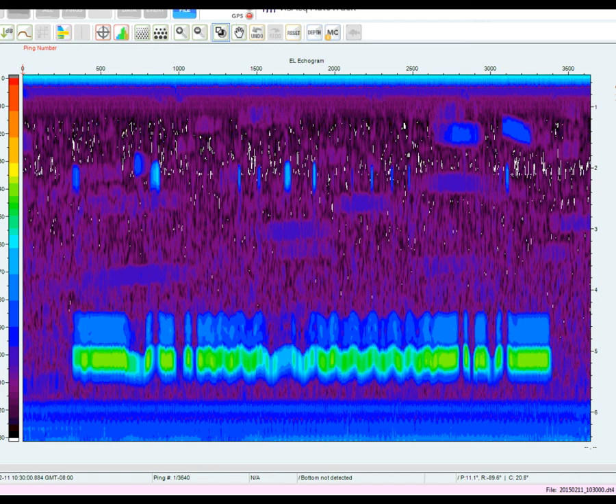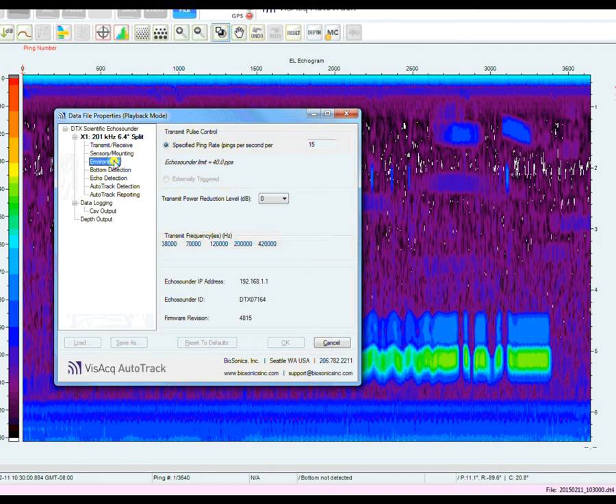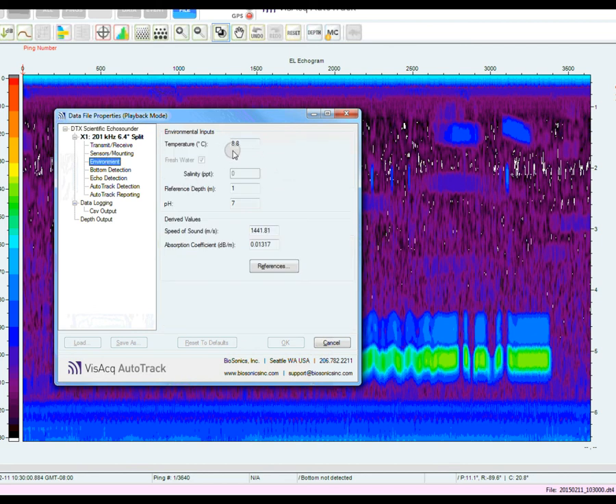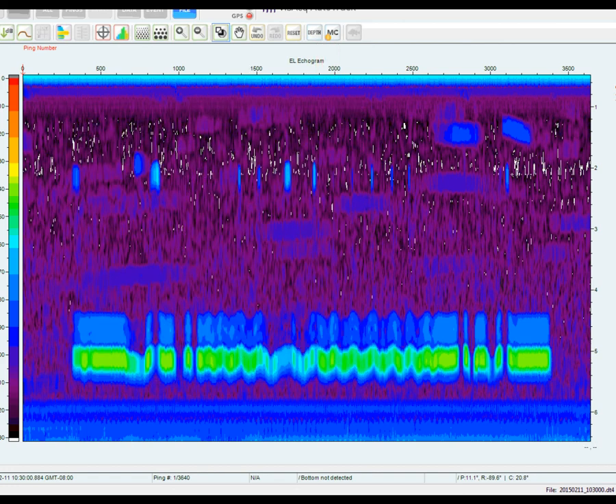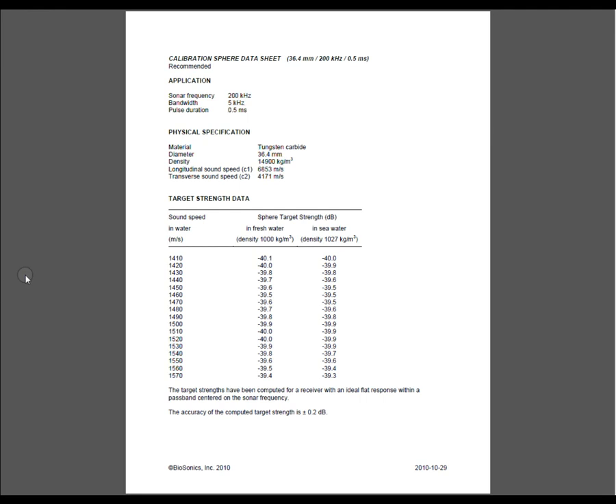VisAcq, we'll go to Playback, View File Collection Settings, and then down in the Environment tab. So you can see we entered a temperature of 8.8 degrees Celsius. We are in fresh water, and if we look, our calculated speed of sound is 1441 meters per second. Okay, so now we'll go back to our sheet, and 1440, that's close. And we just go over to our freshwater column and we look, and it says minus 39.7.